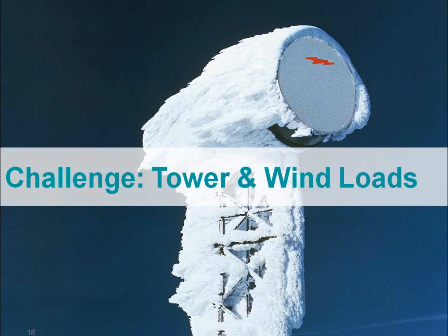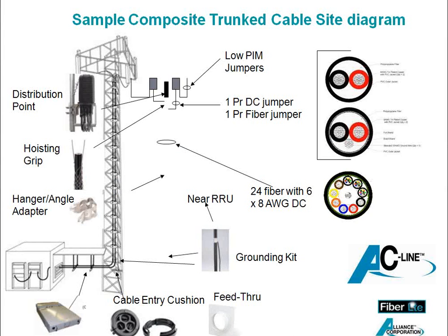One must make certain to factor in the proper ice loading considerations in new tower designs and ensure, when retrofitting an existing tower, that it can handle these new loads. Even if you're in an area that is not high risk, it is always a good idea to include the consideration, thereby resulting in a much more conservative design.